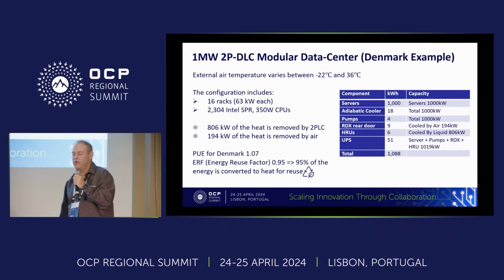When you go back to that modular data center that we showed in the beginning, what we have is 16 racks, 63 kilowatt in each rack. Those are CPU racks that use the C series from Dell, so it's an HPC kind of configuration. In that model, we have 2,304 CPUs of 350 watt, the SPRs. And of the total power, we see that 806 kilowatt are being removed with the direct-on-chip liquid cooling, and another almost 200 kilowatt removed by air.